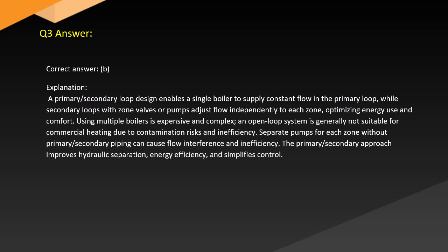Using multiple boilers is expensive and complex. An open-loop system is generally not suitable for commercial heating due to contamination risks and inefficiency. Separate pumps for zones without primary-secondary piping can cause flow interference and inefficiency. The primary-secondary approach improves hydraulic separation, energy efficiency, and simplifies control.